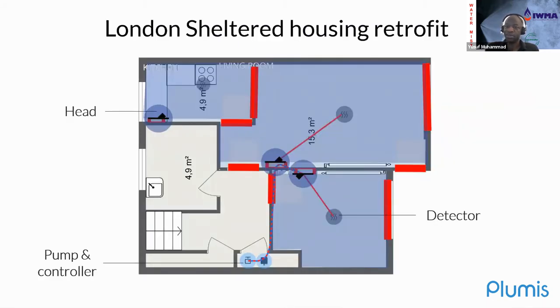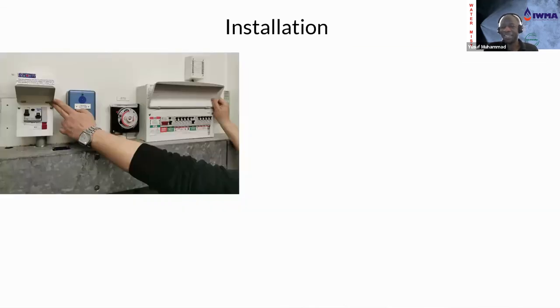So we were selected because it meant that they could address the risk in these particular buildings with a head in the kitchen, the living room, and the bedroom, as well as that detection. And installation was fairly straightforward and could be done in a single day. So the key part of the installation is installing it on a separate circuit, so that it's not going to be tripped if there's an electrical fire that trips the fuse, say, in the protected space. It's on an entirely independent circuit.